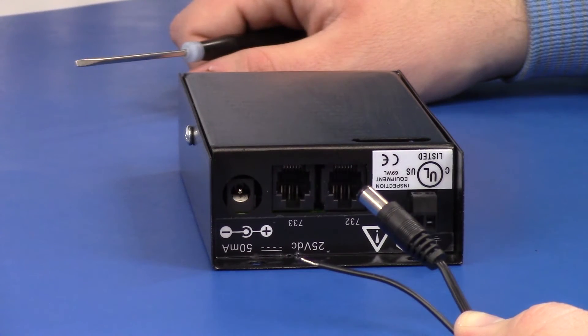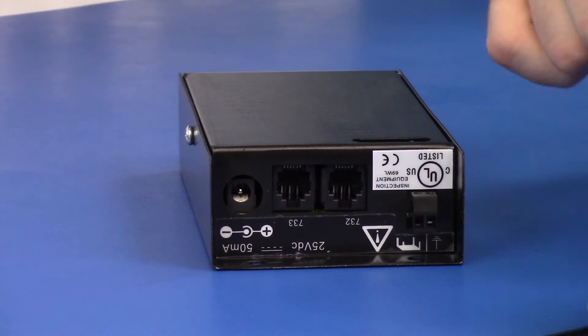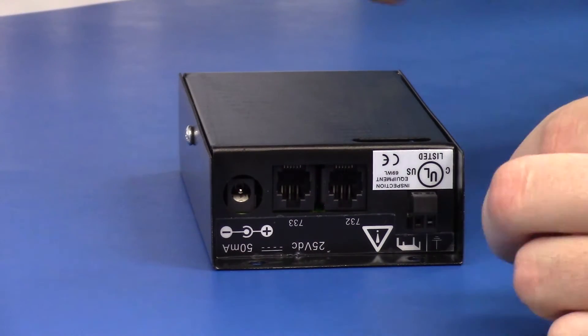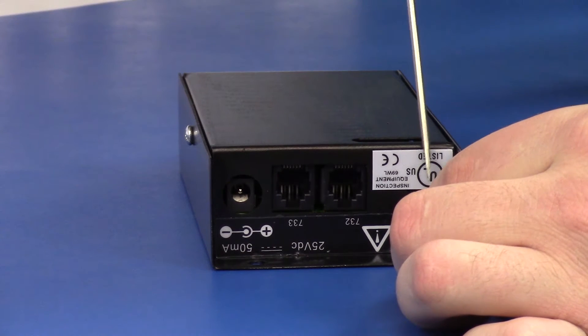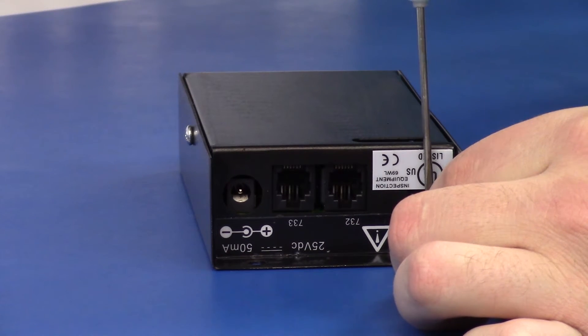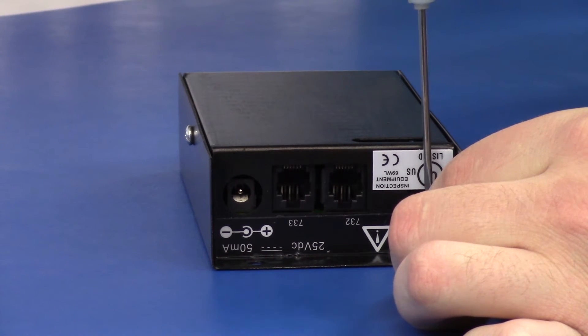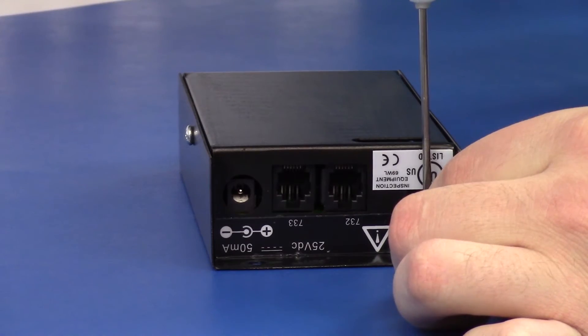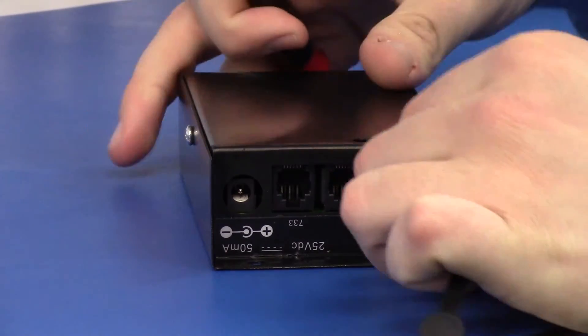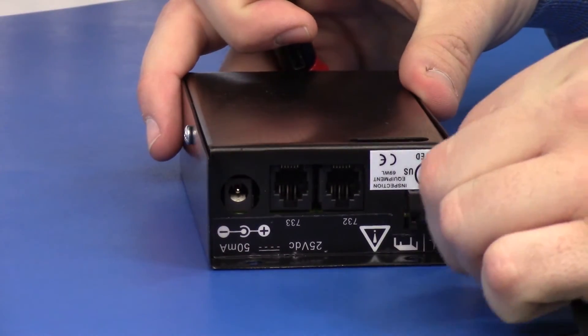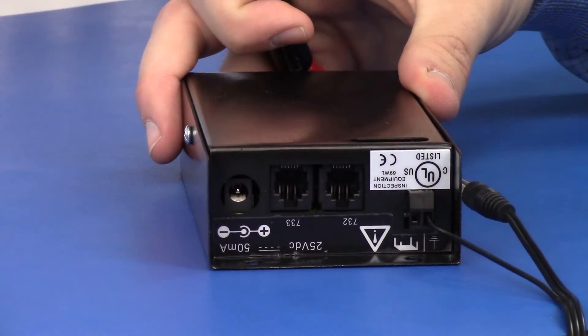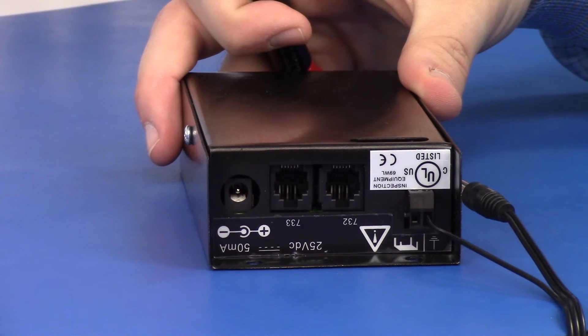To set up the SES724 Workstation Monitor, first connect the ground wire from the power adapter to the ground terminal of the two-wire terminal block. Use a small blade screwdriver to open the terminal, insert the wire, and then close the terminal to secure it.